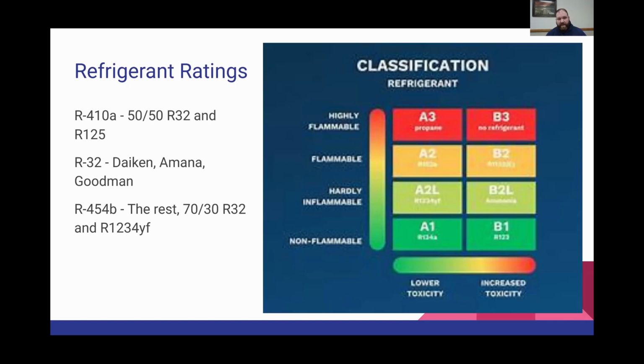The two refrigerants you're hearing about a lot now are R32 and R454B. Daikin, Amana, and Goodman have chosen to go the R32 route. Everybody else went to 454B. Now, just so you know, 454B is basically a 70-30 split between R32 and R1234YF. The automotive industry went R1234YF. So if you're saying, "I don't want this R32," every piece of new refrigerant is coming with some level of R32 in it. The question is, is it pure R32 or is it mixed with 1234YF? There are some reasons I prefer R32 that I'd be happy to share, but I won't waste your time with that right now.